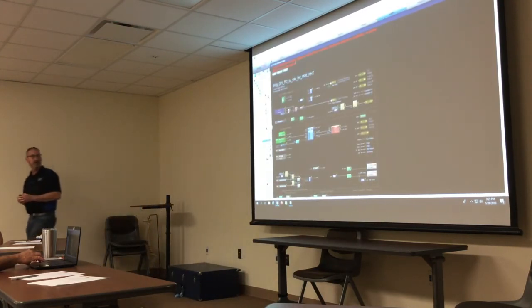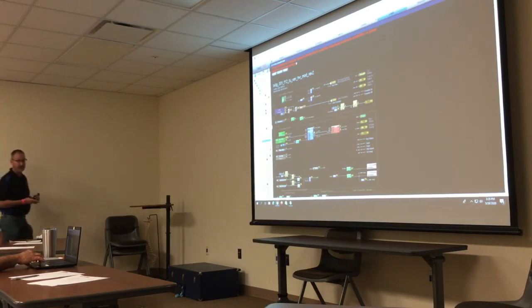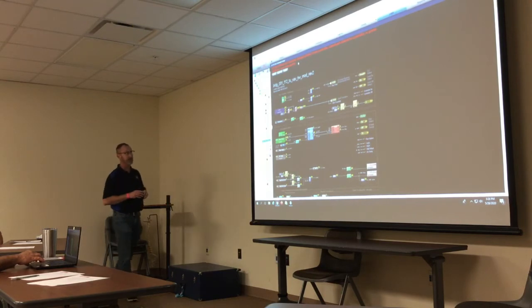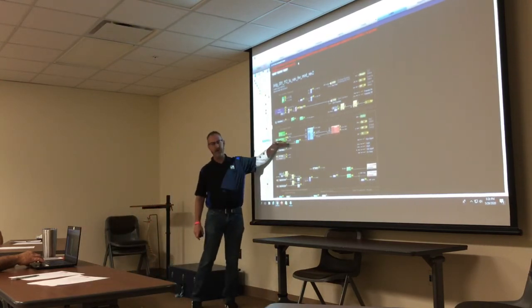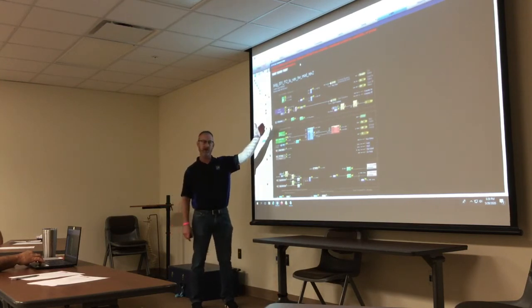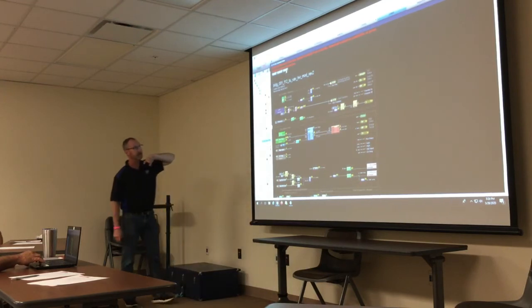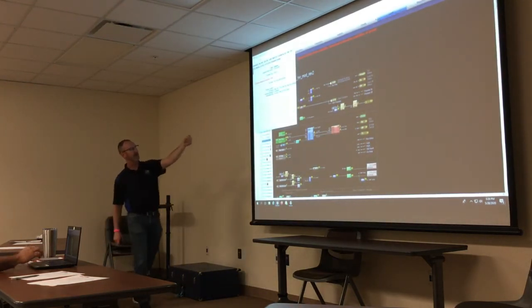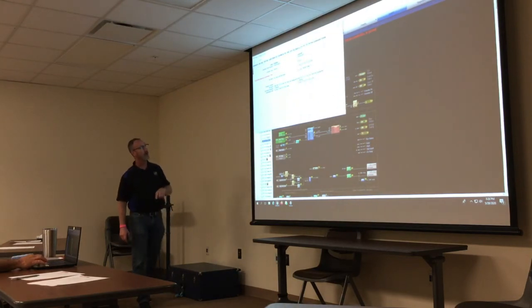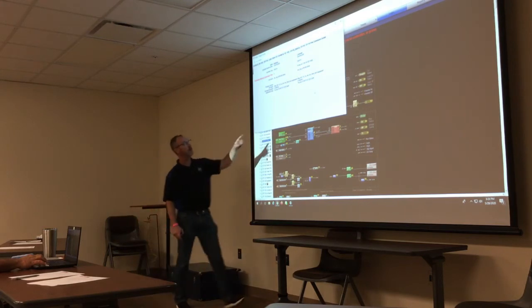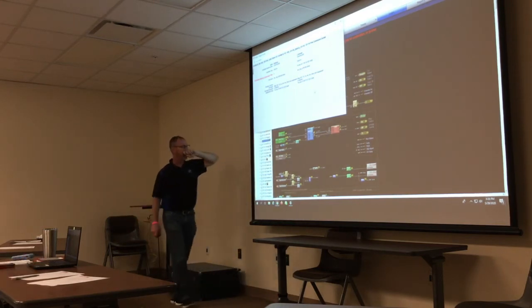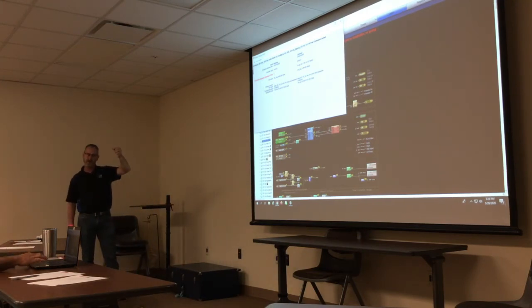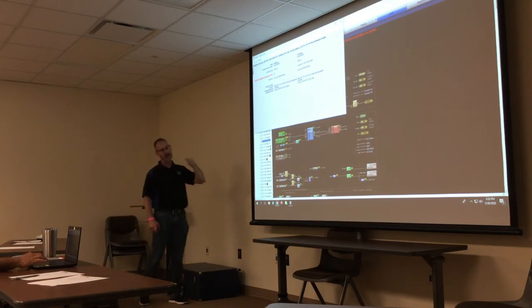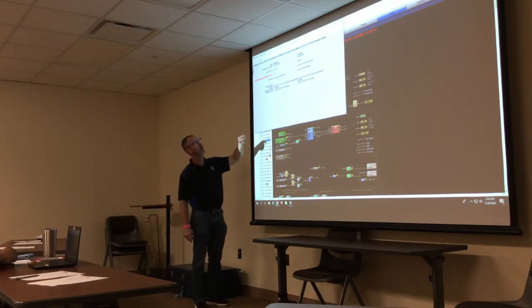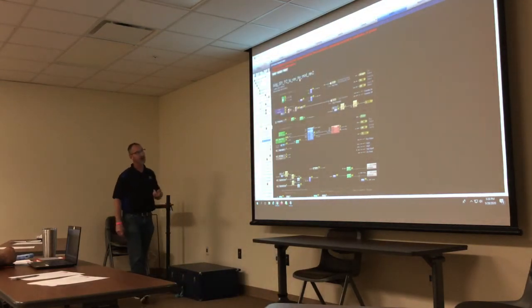Okay, I'll go back to the graphics. All right, so you may see this, especially right now with commissioning and everybody going through the system. What it means is that the controller has information different than what the server has for it. So if you click on details, pull that window out a little bit larger, it'll actually tell you what it sees as the difference. So this particular one is missing its download date. That's probably one where the technicians downloaded it locally, and the server hasn't gotten that information up to it yet.